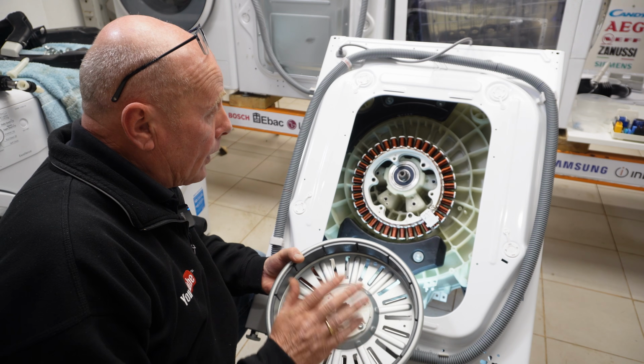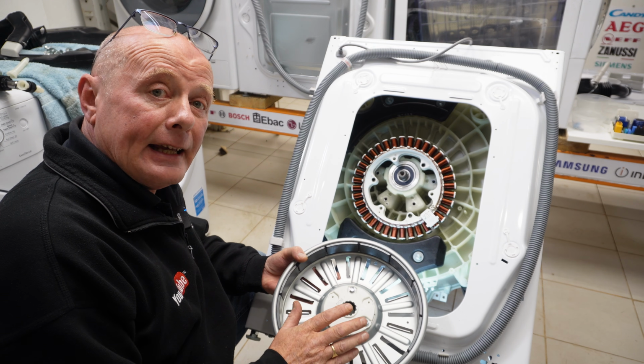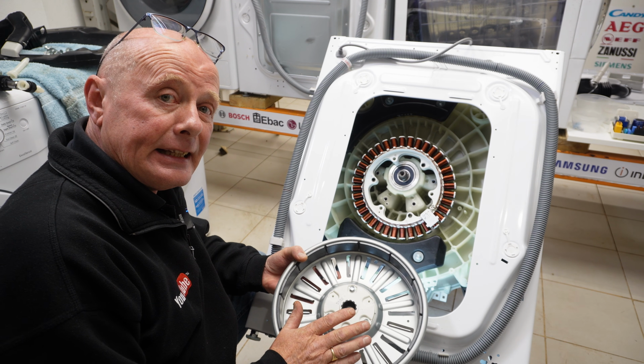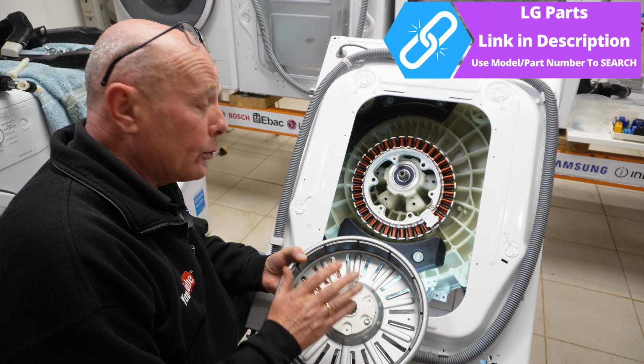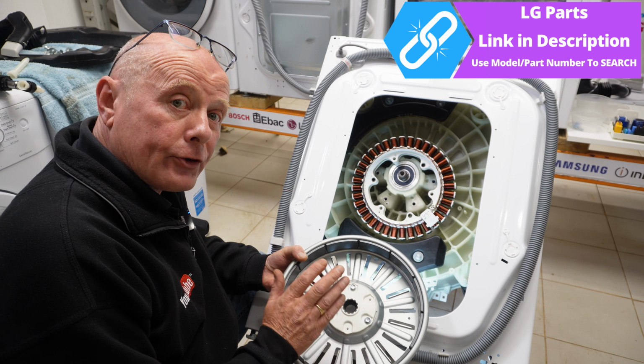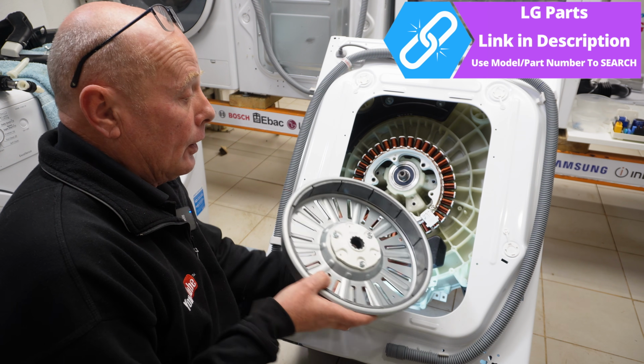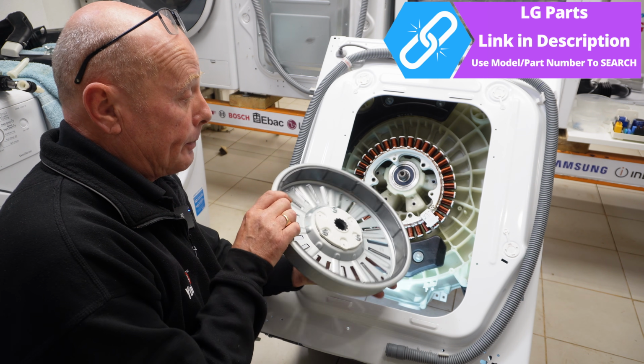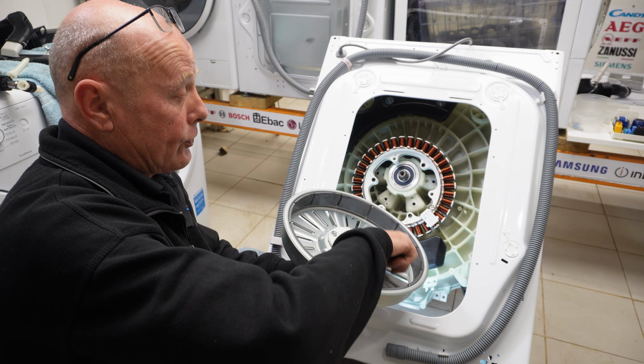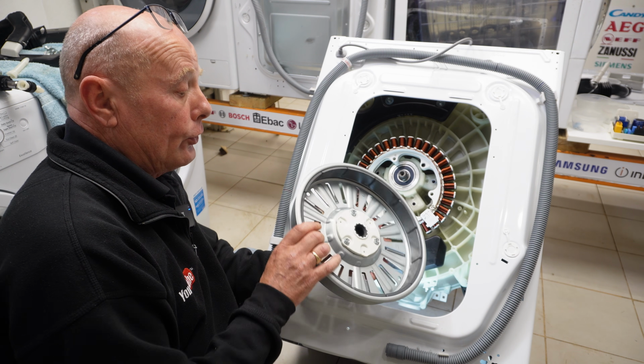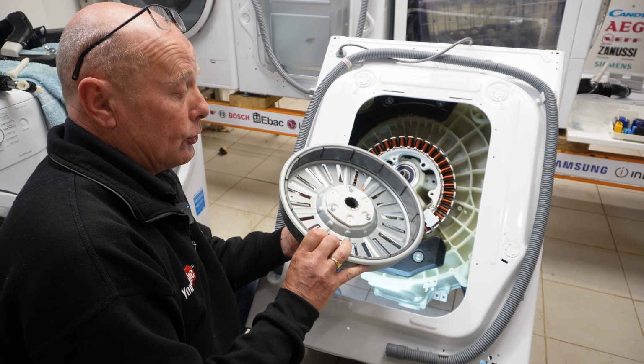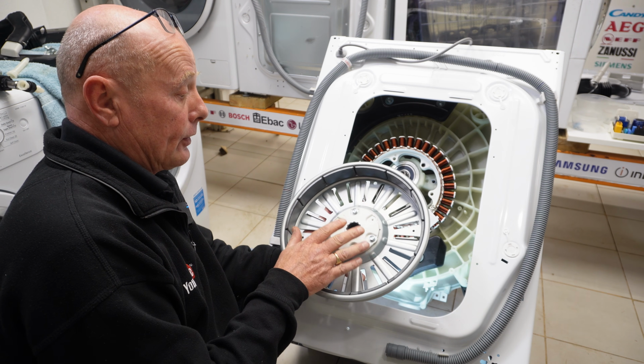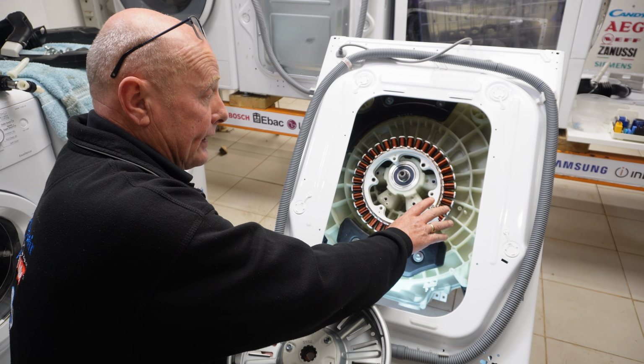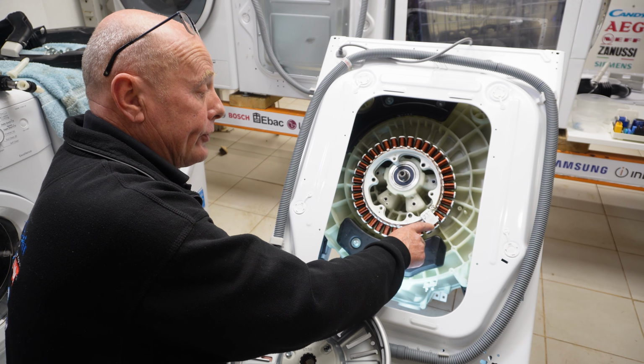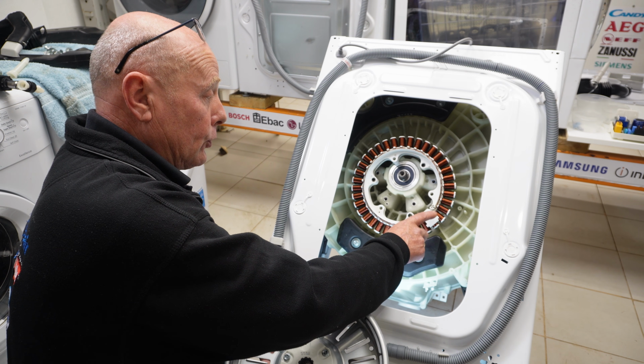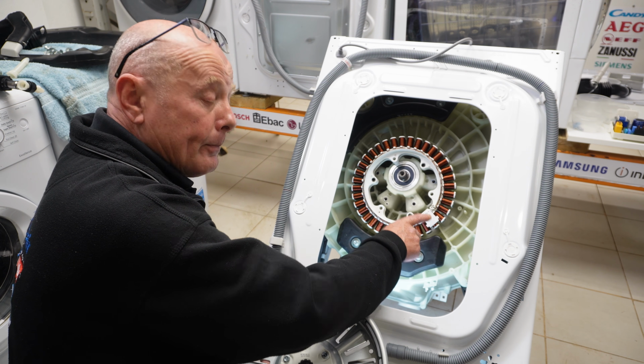Okay, just quickly while we're at this point, LE, SE and CE are all somehow related to the motor fault system. Now, quickly going around the outer part of the stator, you can see these magnets. Make sure that all those magnets are in good condition. The next thing that we want to deal with is the motor itself. You are able to test the motor. It's a 3-phase motor. All the fields should be equal.